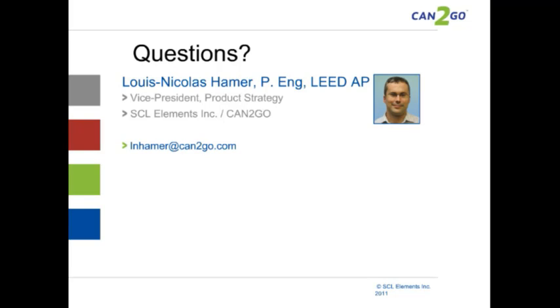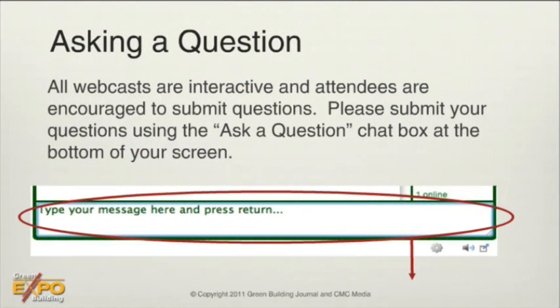Yeah, that's a good question, and you have to look at the type of wireless technology you're using. I talked a lot about EnOcean and Zigbee, so let me give concrete examples. With EnOcean, you're looking at self-powered end devices which don't require any batteries, so that's quite interesting. Because you don't have batteries, the range between the EnOcean end device and the controller is somewhat limited. In a building, you're looking at about 50 to 90 feet, depending on obstacles and wall composition. Within a zone, normally you're able to have 50 to 90 feet between the controllers and end devices. Then with Zigbee, there are many Zigbee end devices out in the market.